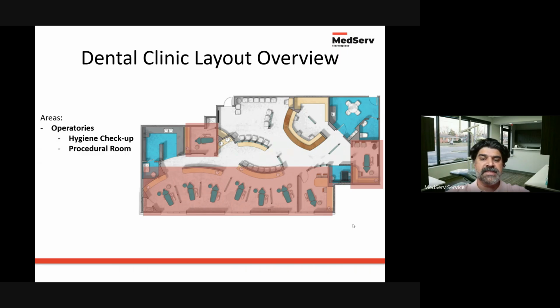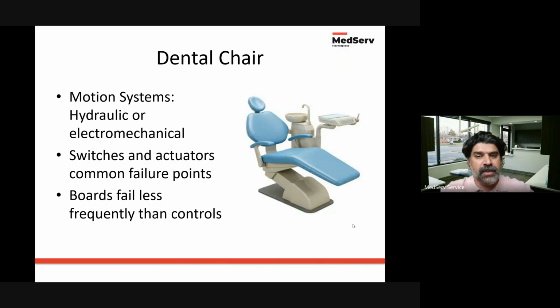And so as this becomes the entry point for most technicians, this is where we hear a lot of the complaints. One of the biggest initial ones is the dental chair itself. This is the foundation for the operatory. It's where the patient actually sits down, and that's where all the procedures happen too. As a chair, its primary function is to hold the patient, and it's supposed to be adjustable. As you may recall, being in a dental chair, they put you back or put you up at different angles to make sure they get the right angle and the right approach for what they're trying to do.